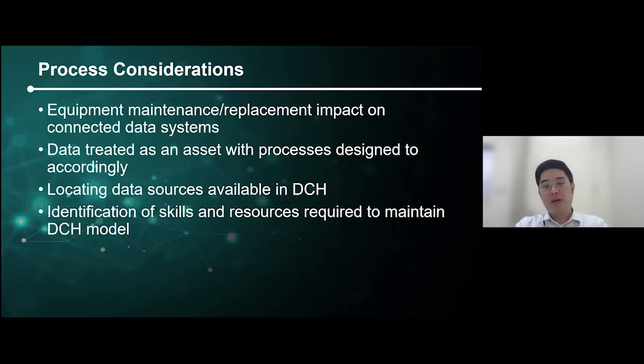We actually saw this in real life. One of the City of Melbourne PV microinverters failed on site and was replaced, in a building we'd already connected and configured within DCH. We found that in replacing the microinverter, the PV system understood it was a new microinverter with a new ID number. From the PV system's side, it worked fine - there were no issues connecting to the point again. However, the data point went offline, and it was only through investigation that we identified there was a fault with that particular unit. The unit was replaced and there's now a new ID associated with it.